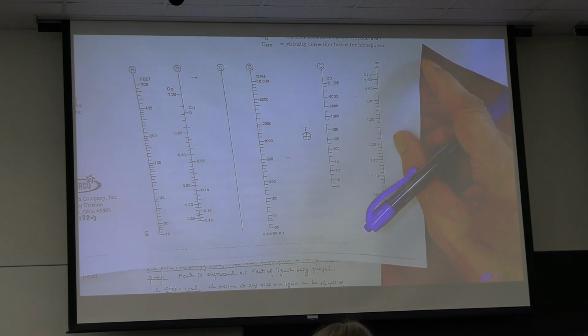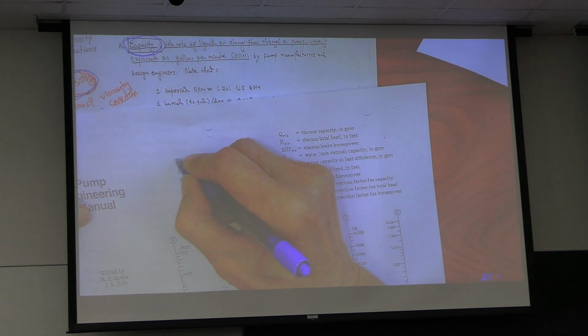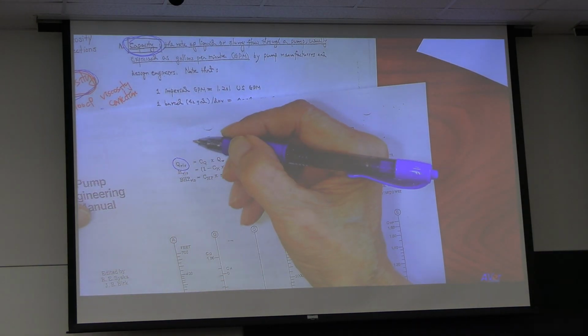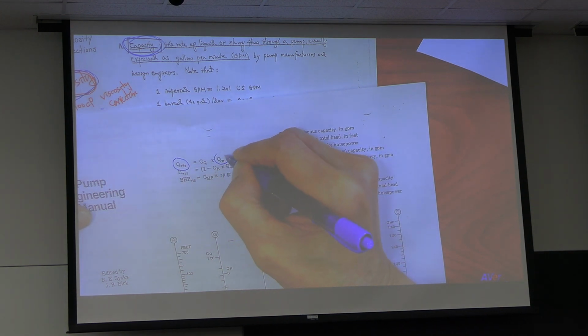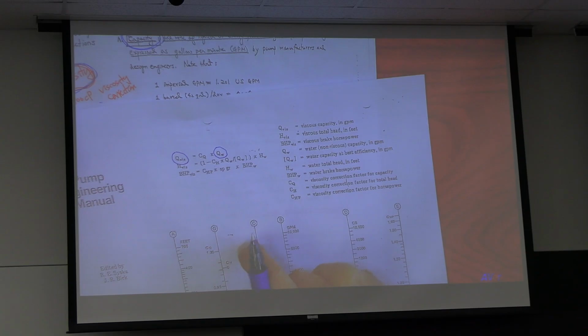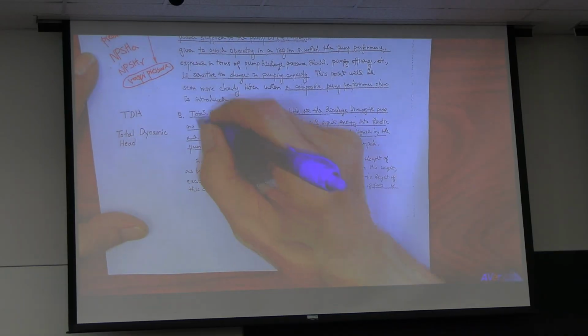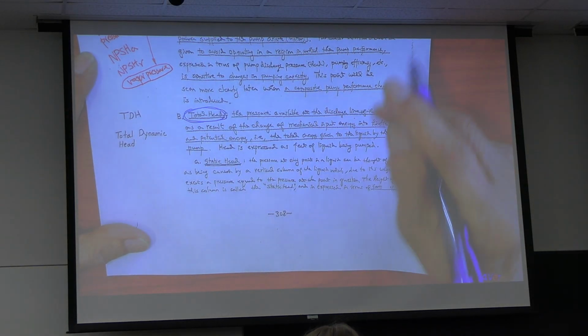From a viscous flow rate, what is the equivalent water flow rate on the pump curve? We're going to learn this, okay? All right. Total dynamic head. This is the most tedious part of pump sizing.